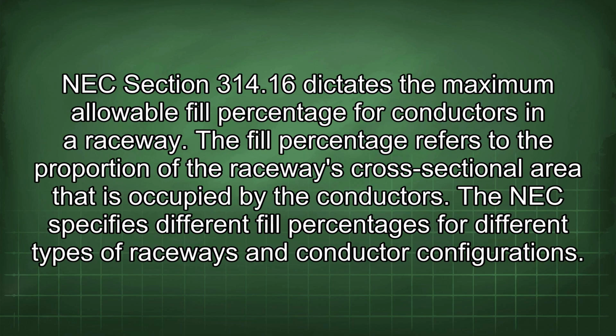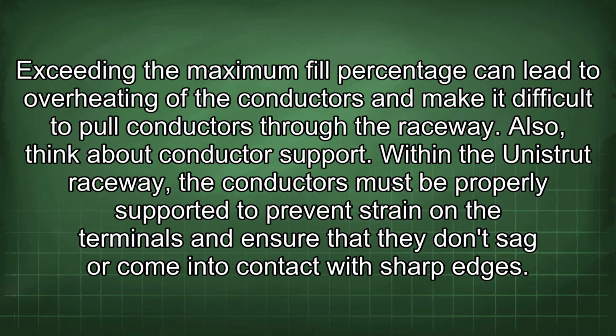NEC Section 314.16 dictates the maximum allowable fill percentage for conductors in a raceway. The fill percentage refers to the proportion of the raceway's cross-sectional area that is occupied by the conductors. The NEC specifies different fill percentages for different types of raceways and conductor configurations. Exceeding the maximum fill percentage can lead to overheating of the conductors and make it difficult to pull conductors through the raceway. Also, think about conductor support.